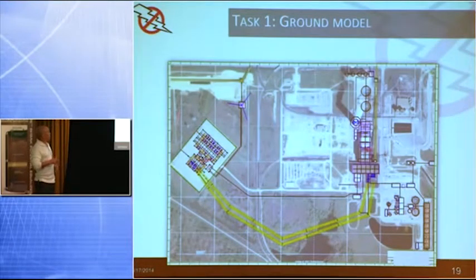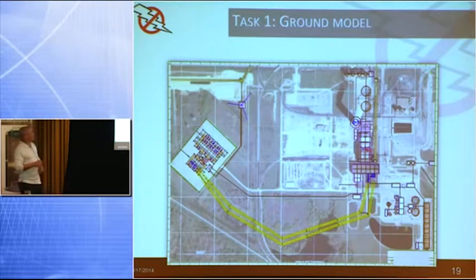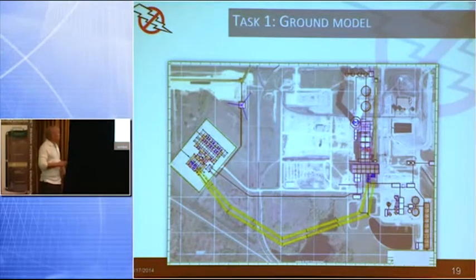Here, you remember the ground drawings I was showing you earlier. We will also lay this over any type of satellite images and adjust it to scale. That becomes important later on because we even use GPS within this. So this is a facility that we did out in the southeast, where they were having some issues with lightning tripping the facility offline. We can get to this a little bit later, but essentially you're looking at about a quarter mile between the substation and the actual generation facility.